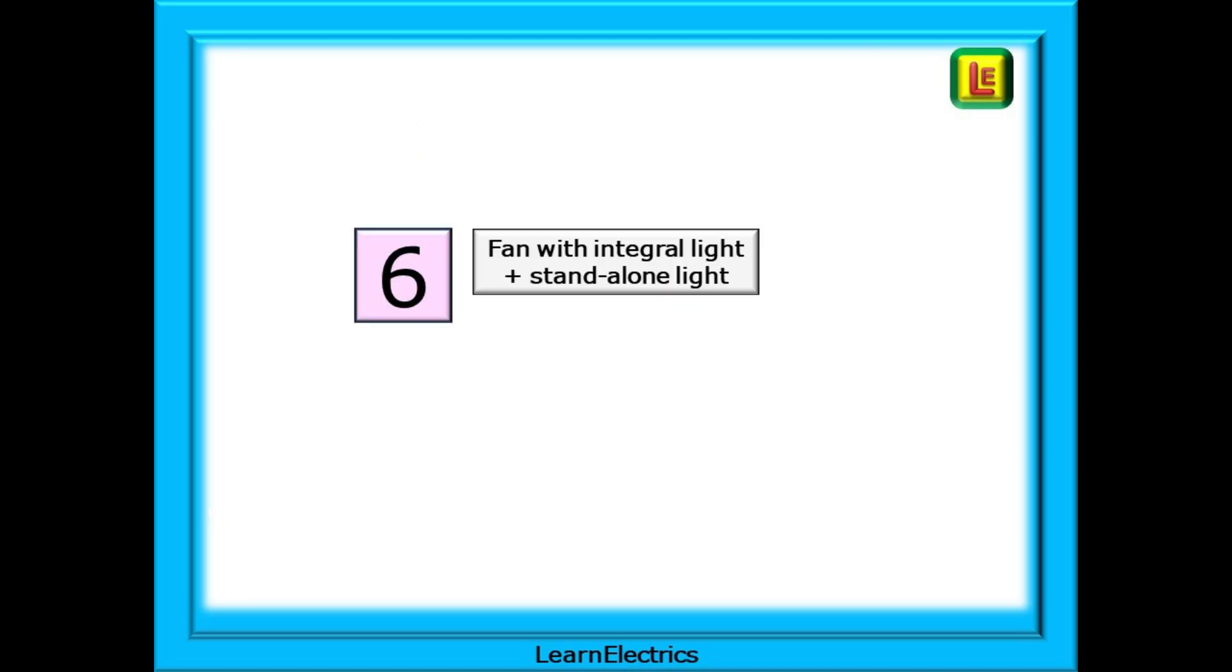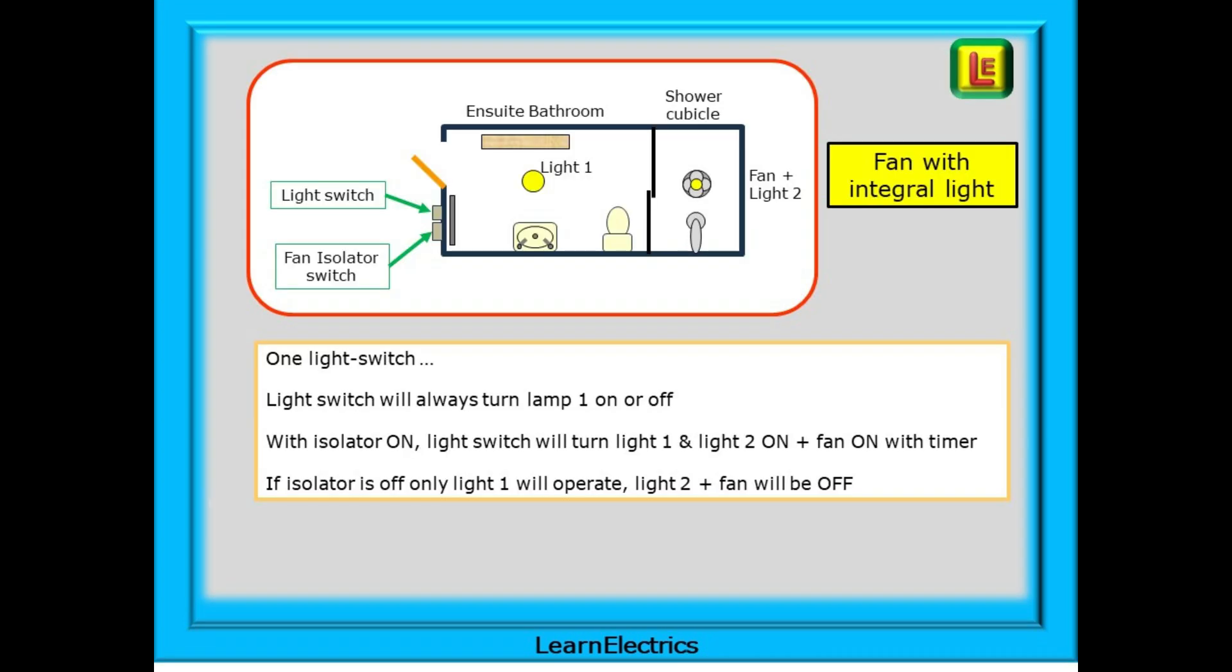Another method that you will come across is a bathroom with two lights. One light is standalone and the second is integrated into the fan. The sketch shown gives a basic layout of this method in an ensuite bathroom. One light is positioned more or less central over the wash basin and the second light is integrated into the fan that is installed in the shower cubicle. Only one light switch was used in this installation. The light switch will always turn lamp one on or off. With the isolator on the light switch will turn light one and light two on and the fan and timer function also. If the isolator is off only light one will operate with light two and the fan both off.